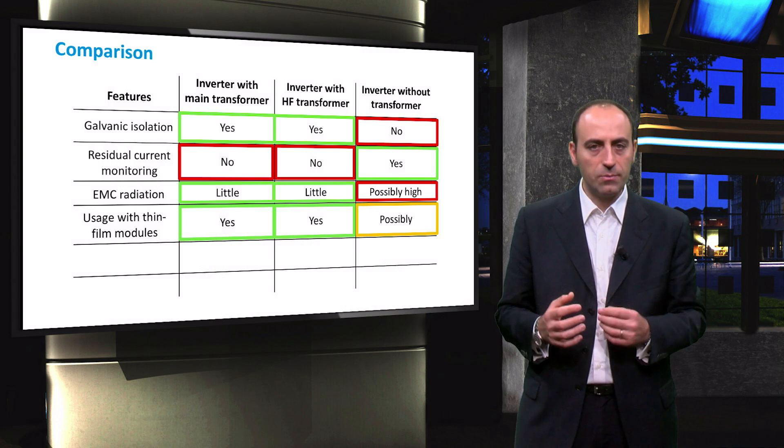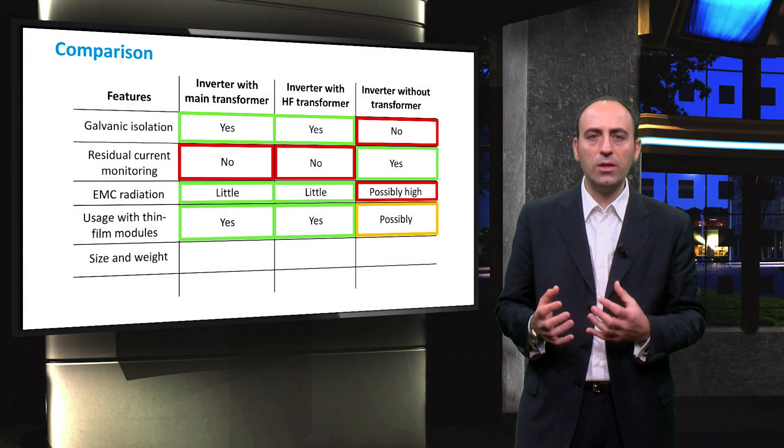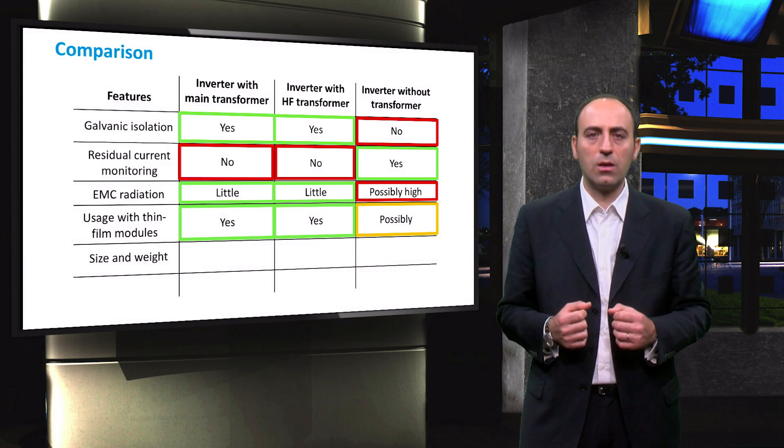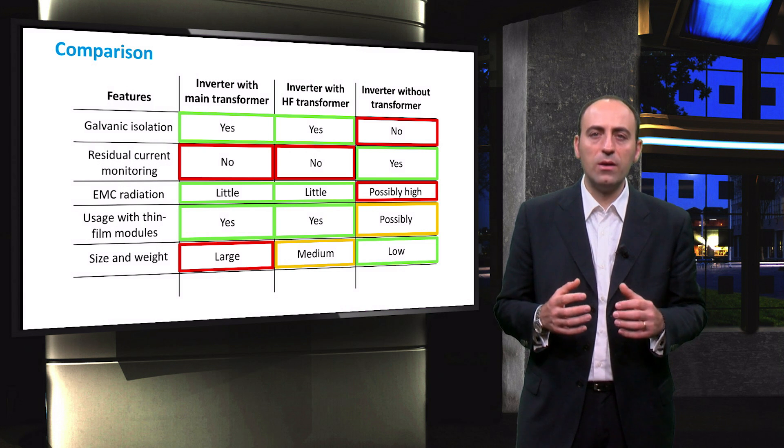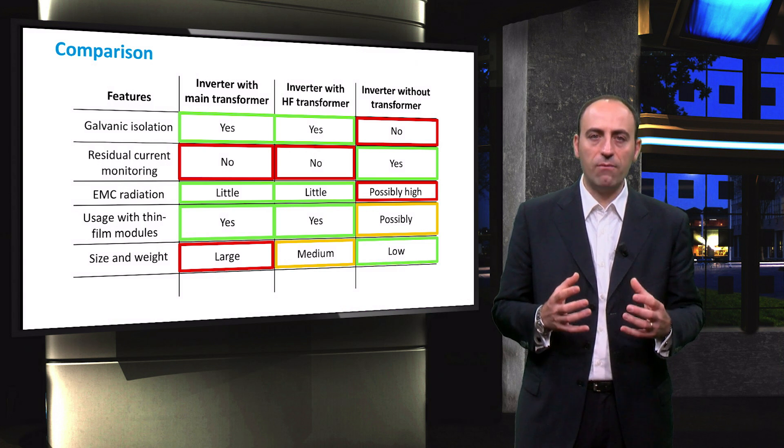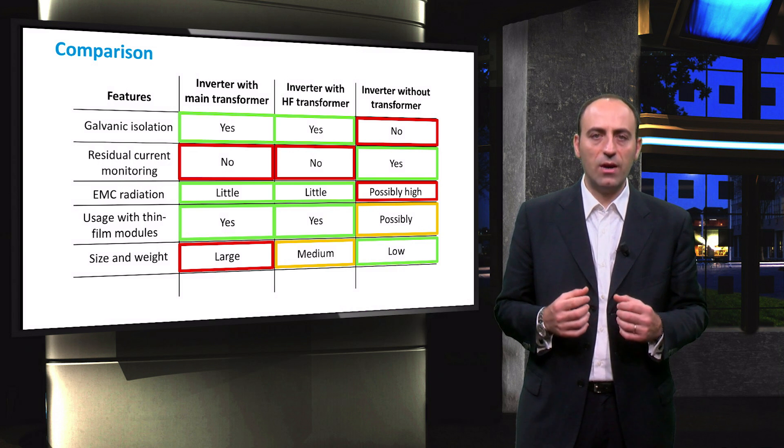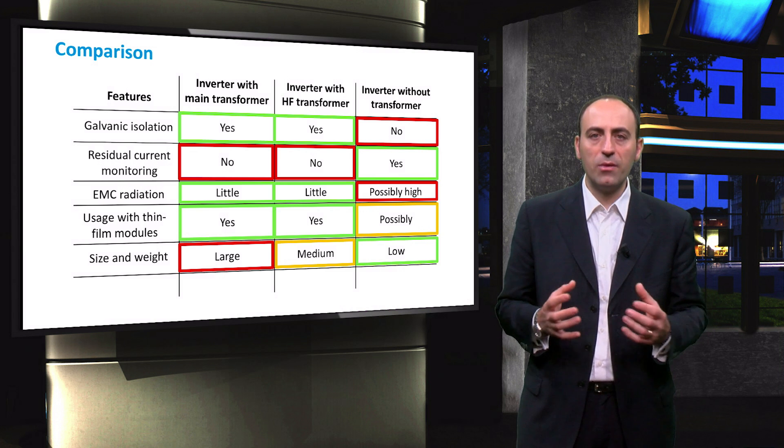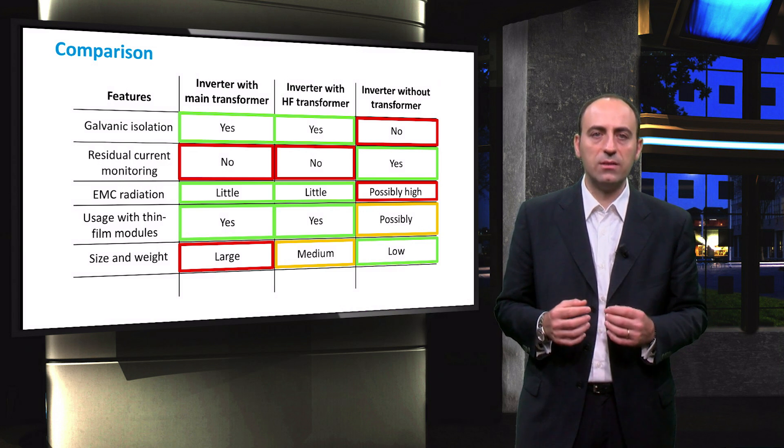Another crucial aspect, when a system design is performed, is the size and weight of the inverter, especially for stand-alone and rural applications. As we mentioned before, the main transformer is particularly bulky and heavy, while the high-frequency transformer is a smaller and lighter device. The transformerless inverter is clearly preferable if the PV system requires a lightweight and small-sized device.